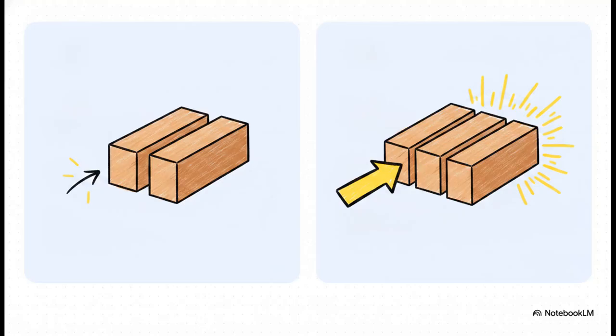Let me give you an example. A 1250 amp board is typically going to run 2 bus bars per phase. But if you step that design up to a 1600 amp rating, those 2 bars just won't cut it anymore. You physically have to have 3 bus bars per phase. The current literally dictates the amount of physical copper.